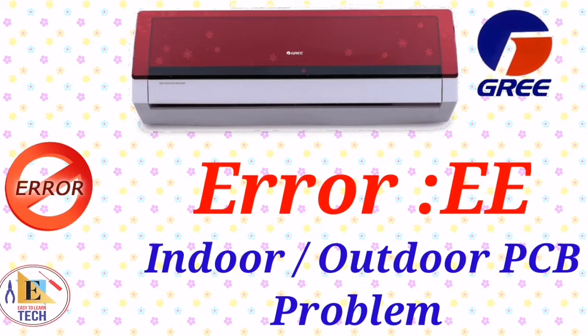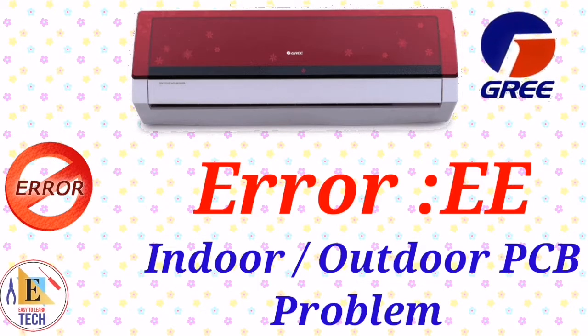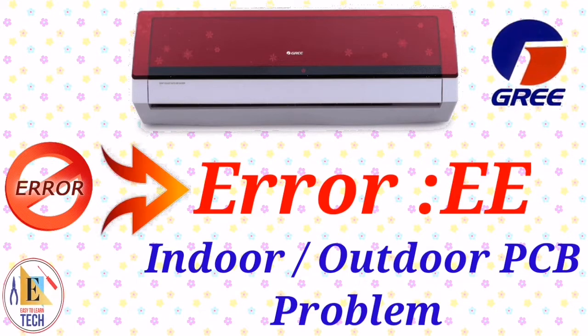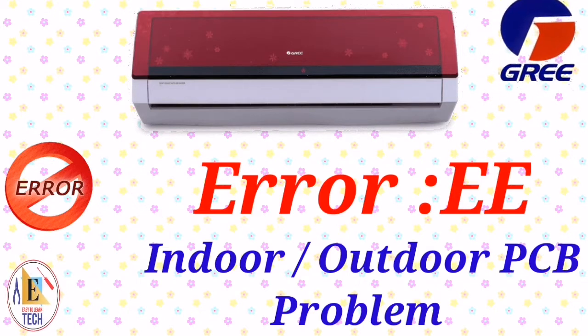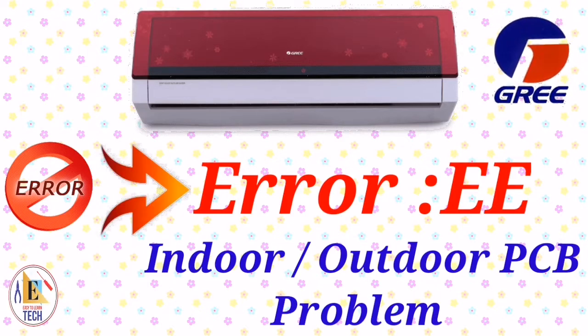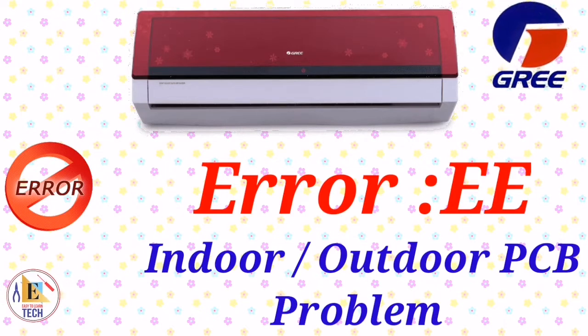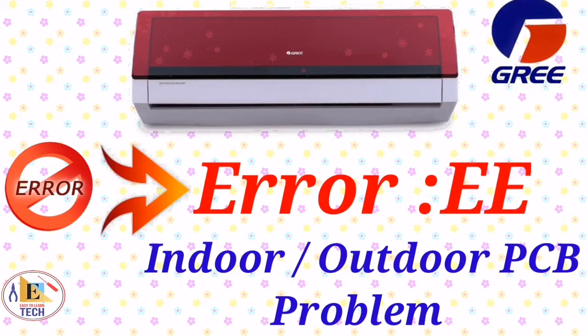In this error, you will find one thing: either the indoor PCB will be faulty or the outdoor PCB will be faulty. You have to check both PCBs perfectly and make sure which PCB is faulty, and you will get the solution for this error.